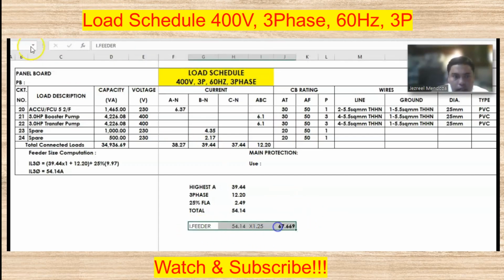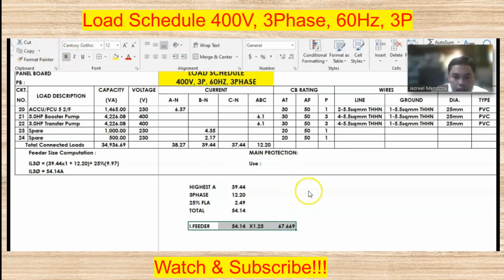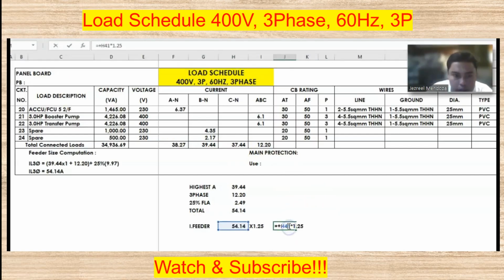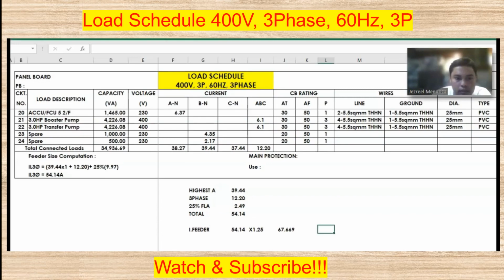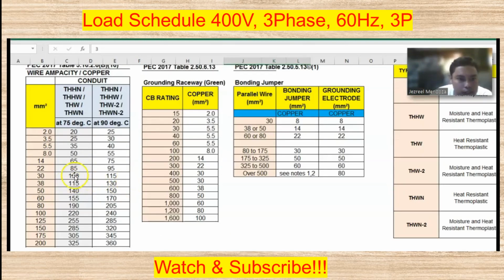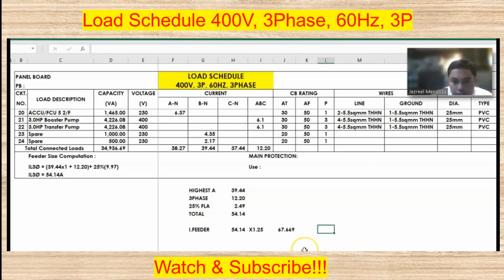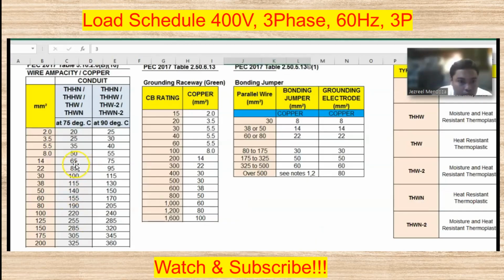So what is the size conductor of our panel board? If we look to the PEC, that is 67.669. We can use 14 square mm, that is 65 amperes.